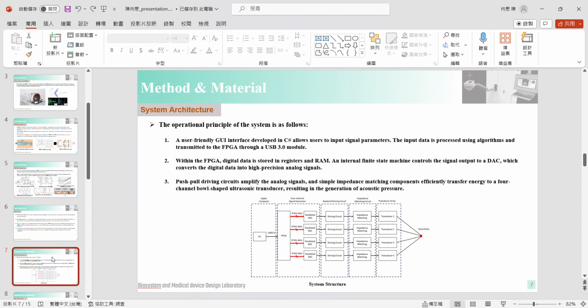The operational principle of the system is as follows. First, a user-friendly GUI developed in C# allows a user to input signal parameters. The input data is processed using algorithms and transmitted to the FPGA through the USB 3 module. Second, within the FPGA, digital data is stored in registers and RAM. An internal finite state machine controls the signal output to the DAC, which converts the digital data into high precision analog signals with a phase delay for each channel. Third, push-pull driving circuits amplify the analog signals, and simple impedance matching components efficiently transfer energy to a 4-channel bowl-shaped ultrasonic transducer, resulting in the generation of acoustic pressure.